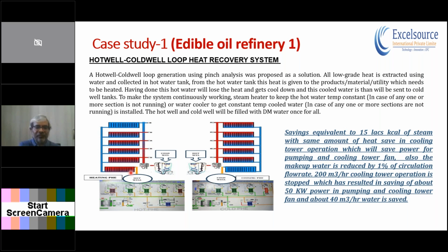By doing this, we are taking out all the low grade heat which at that time was being thrown into the cooling tower. We have taken that heat and generated water up to 90 degrees Celsius. That water we have distributed across the plant, and the heat is given to the product to be heated to a certain temperature, like 75 degrees Celsius or 80 degrees Celsius. Then, after giving the heat, the water comes back at about 30 degrees Celsius. Whatever the feed water or product temperature is, plus 5 degrees Celsius is the return water temperature.